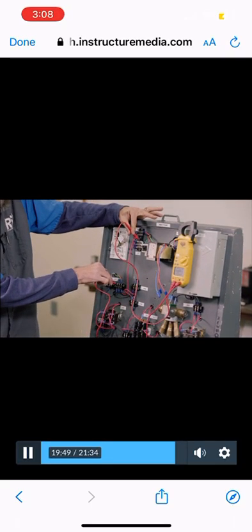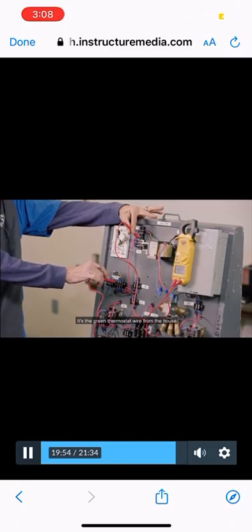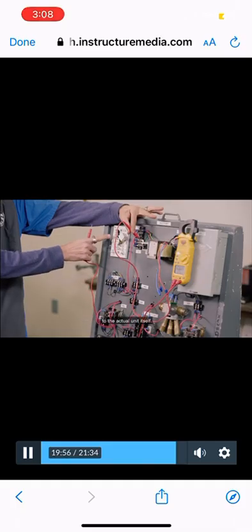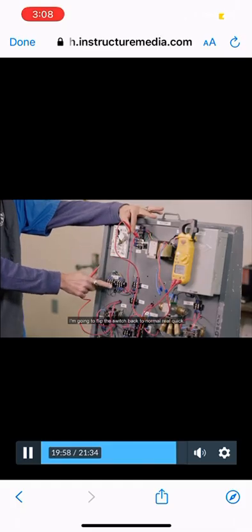We're looking for some voltage and I don't have any. So I'm going to look at who tells these two what to do, which would be my green circuit, that thermostat. So I'm going to go from common on my transformer to the green circuit because that's what feeds it. And I'm looking for voltage. Okay, I don't have any. So that tells me I'm already done. It's the green thermostat wire from the house to the actual unit itself.